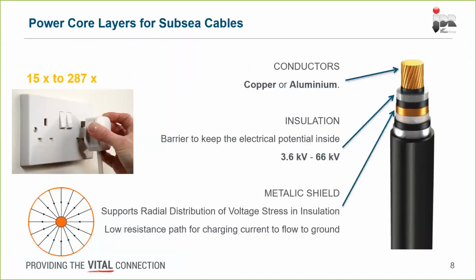In terms of the conductor design, usually the conductors are stranded, which gives them a lot more flexibility than a solid core. They're also made of copper or aluminium. Copper is highly conductive, meaning we can make the core quite small and still carry a lot of current. We've also got aluminium available, which is about 60% as conductive, so we usually need slightly bigger cores if we're using aluminium as the conductor medium.